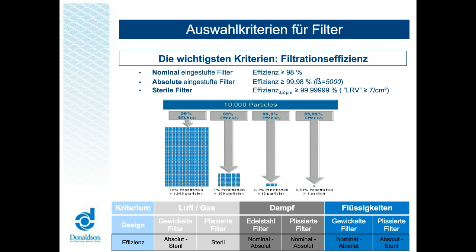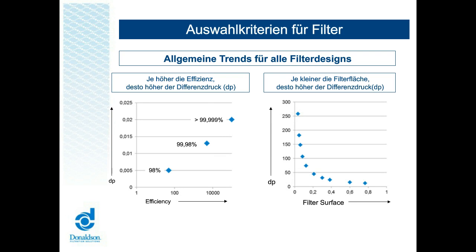Die nächste Frage ist dann logisch: Wie verhalten sich Filtrationseffizienz und Druckverlust zueinander? Je nach Typ, Aufbau und Medien unterscheiden sich die Werte signifikant. Als Grundregel gilt: Je höher die Effizienz, desto höher auch der Druckverlust. Je niedriger die Filtrationsoberfläche, desto höher der Druckverlust. Um diesen inhärenten Nachteil hocheffizienter Filter auszugleichen, sollte die Filtrationsoberfläche vergrößert werden, wobei ein plissierter Aufbau dieser Übung sehr zweckdienlich ist.